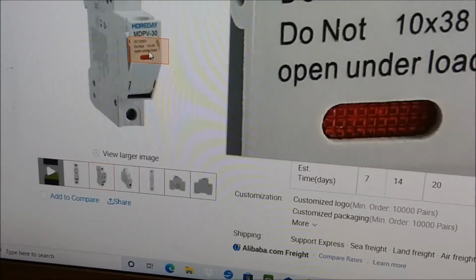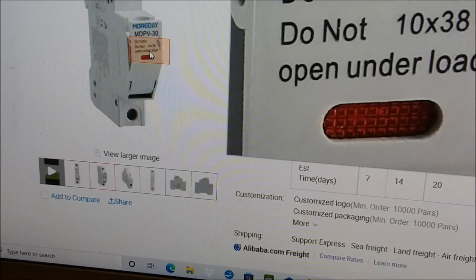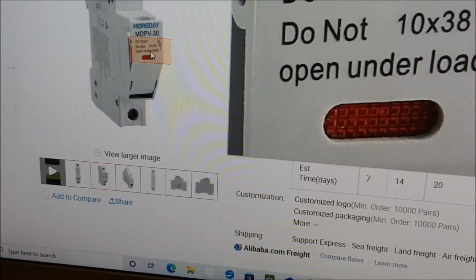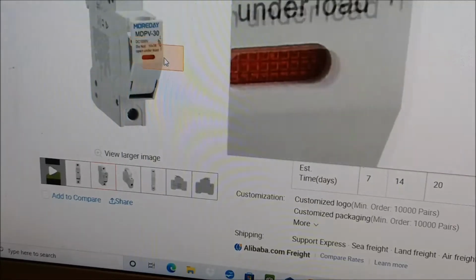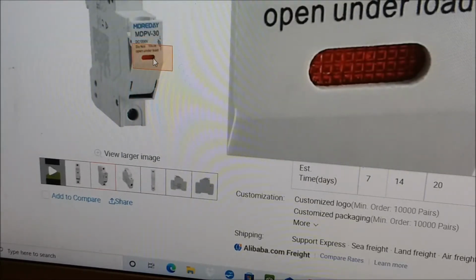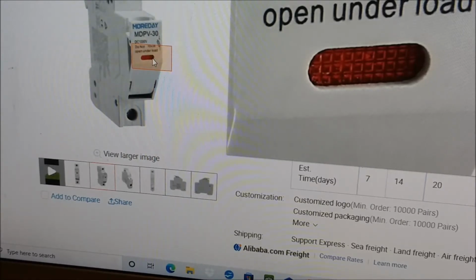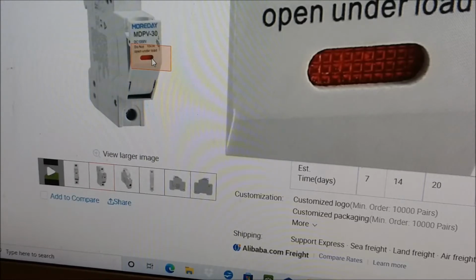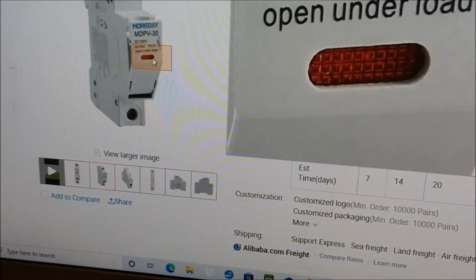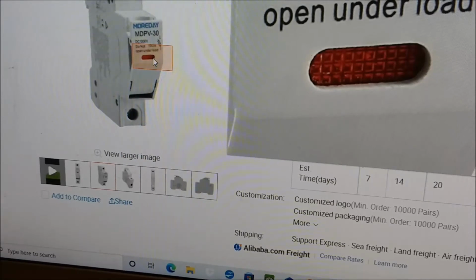Do not open under load. It will blow the fuse if you don't turn the circuit breaker off before you open the fuse holder. Now, if the fuse is already blown, the red thing in the center of the window there, that's an LED light. That'll be on if there's no connection through the fuse. It's got an extremely small current draw to ground, and that will read enough voltage to turn on the LED.